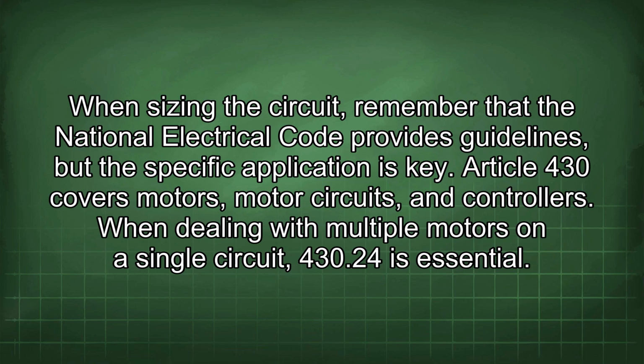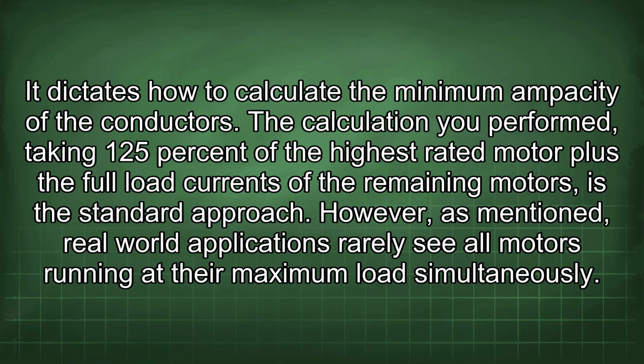When sizing the circuit, remember that the National Electrical Code provides guidelines, but the specific application is key. Article 430 covers motors, motor circuits, and controllers. When dealing with multiple motors on a single circuit, 430.24 is essential. It dictates how to calculate the minimum ampacity of the conductors. The calculation you performed, taking 125% of the highest rated motor plus the full load currents of the remaining motors, is the standard approach. However, as mentioned, real-world applications rarely see all motors running at their maximum load simultaneously.